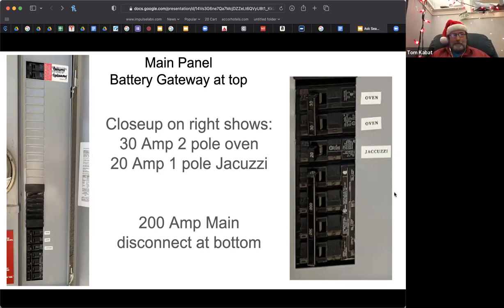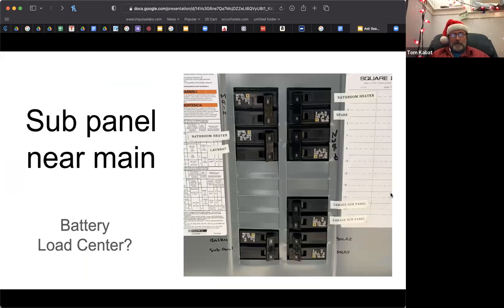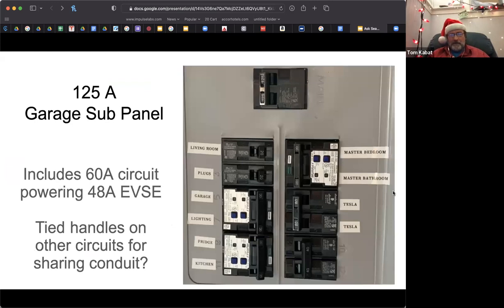I'm going to go pretty quick through the slides. This is their main sub panel. You can see they've got a lot of breaker spaces in there and are using full-sized breakers. Sometimes when things get crowded, we can go from these full-size 1-inch wide breakers to tandem breakers that fit 2 breakers into the space of each inch, so it's a way to fit more on physically.